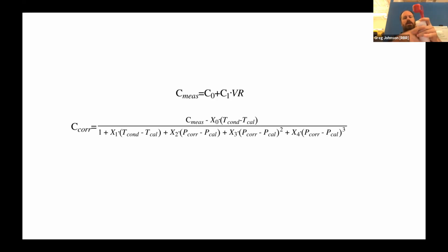or water. So the second ferrite is set up in a receive configuration. And so it also has a coil, and it's looking for any AC current that is induced by a changing electric current passing through the center of that ferrite. And so that second ferrite only sees something if there is current passing through the center of the cylinder. And the first one is responsible for driving something through the center of the cylinder. And the coupling, if you're from an electrical engineering background, you think of it as an N-to-1 transformer, where you've got N turns on this coil and 1 turn of seawater. And the coupling is given by the electrical conductance of, or resistance reciprocally, of the seawater loop. Because we're interested in conductivity, not conductance, we have to do a couple of things to sort that out. And I'll walk that through in a second.